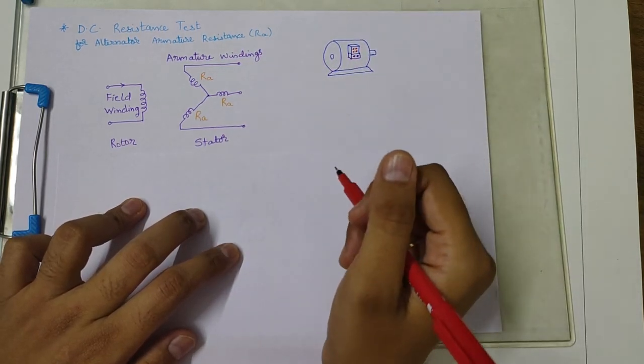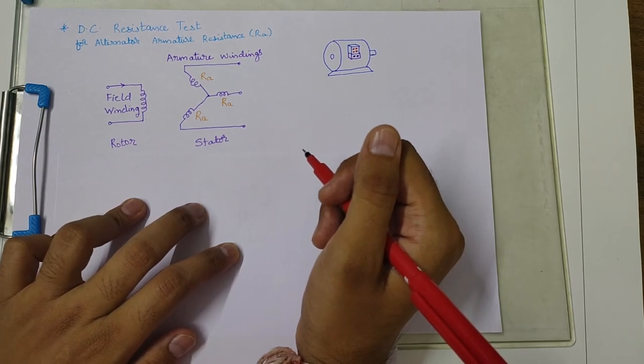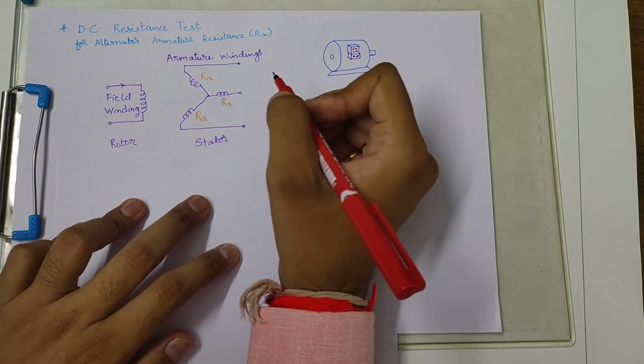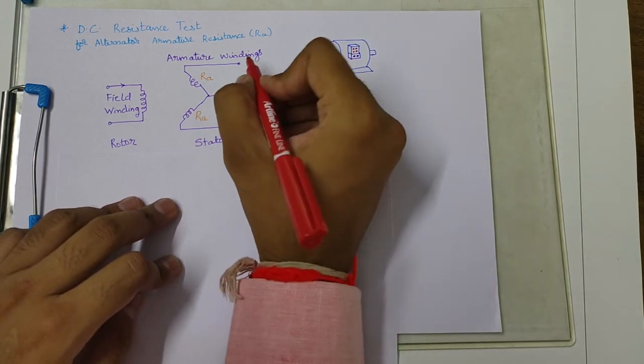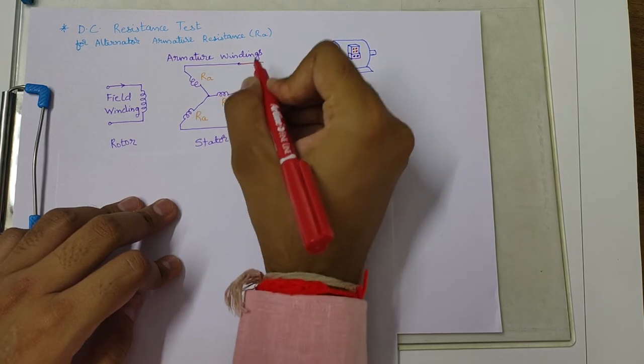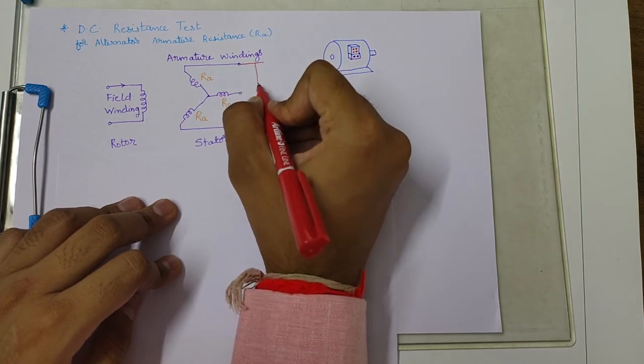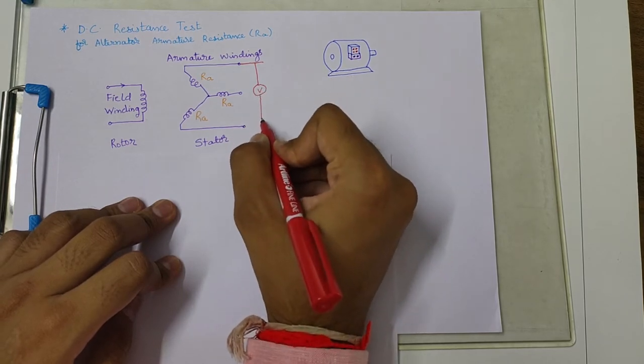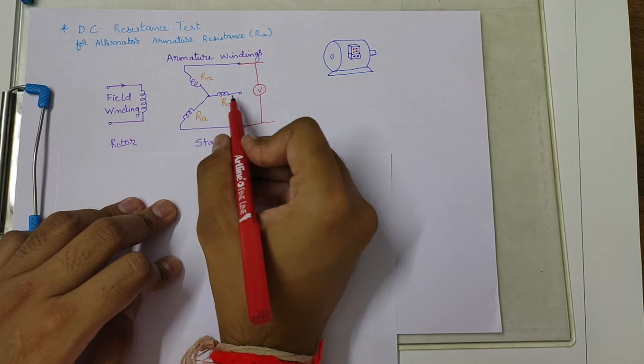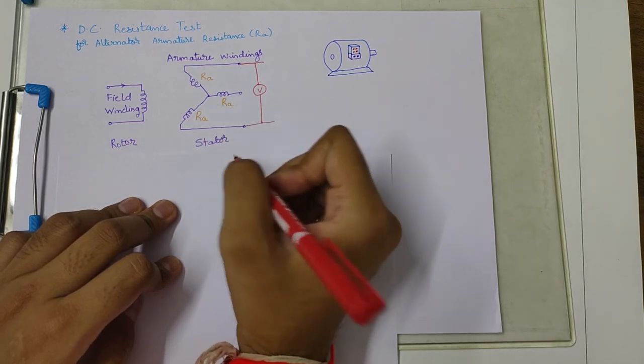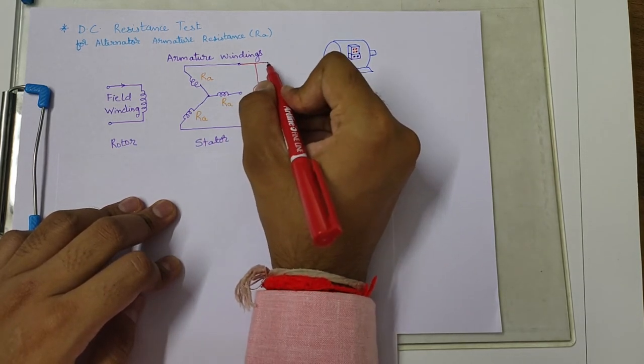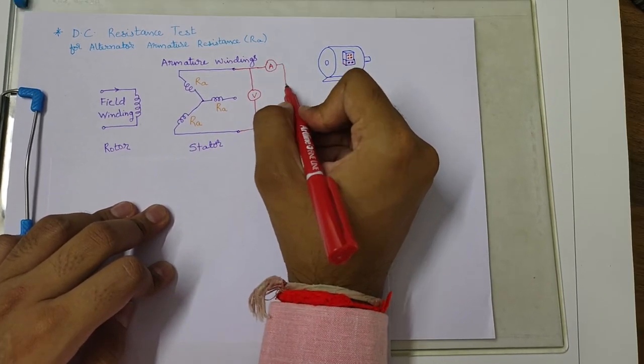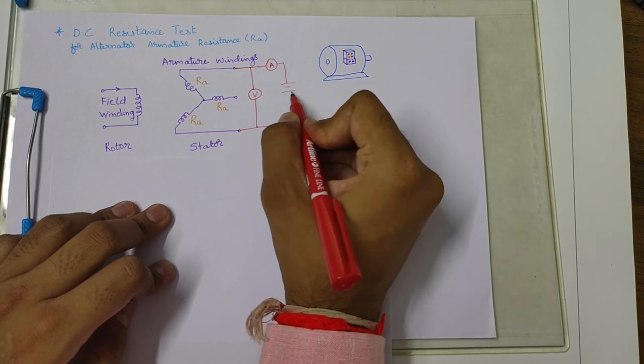As you can see here, I will have only three terminals at the terminal box. So how shall I connect voltmeter and ammeter to calculate the resistance by Ohm's law? First of all, I will connect the voltmeter with any two terminals and I will keep one terminal open, and I will connect an ammeter in series with the windings and provide a DC supply.